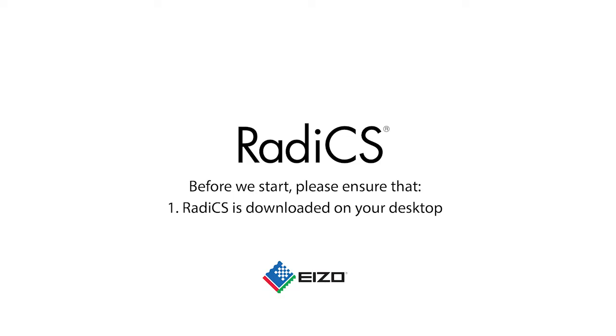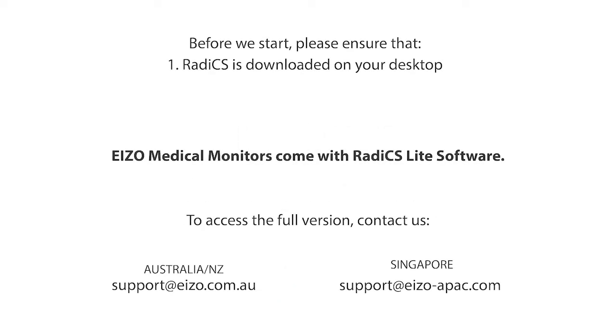Before we start, please ensure that RadiCS is downloaded on your desktop and the USB A to B cable is connected. EIZO medical monitors come with RadiCS Lite software. To access the full version, contact us.